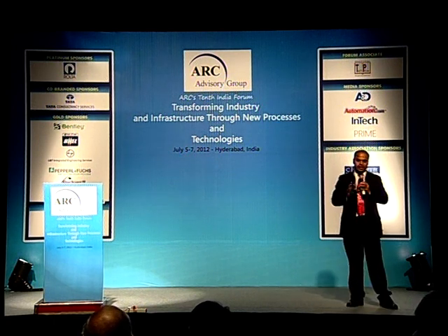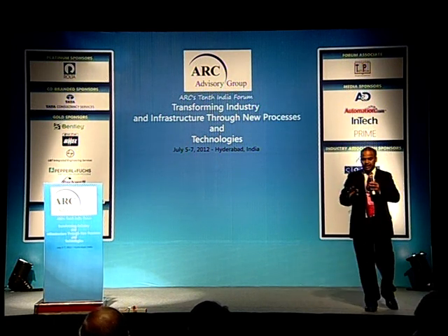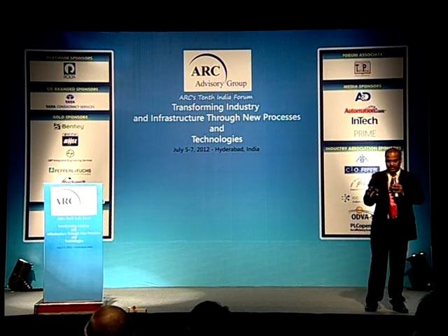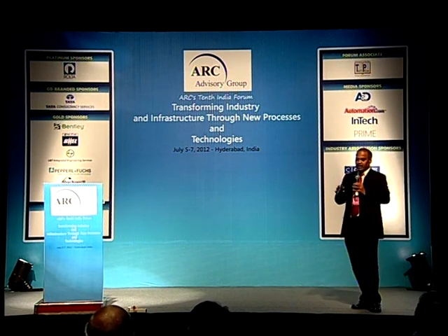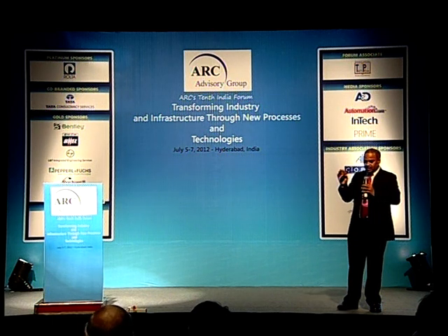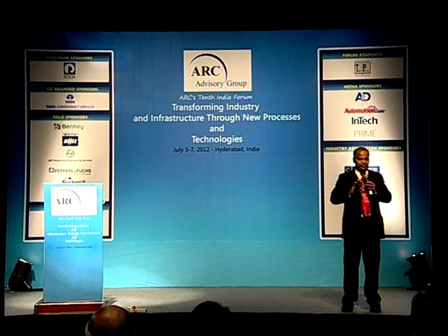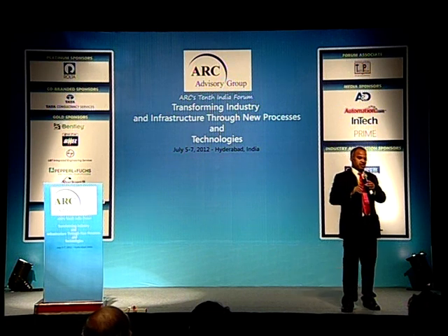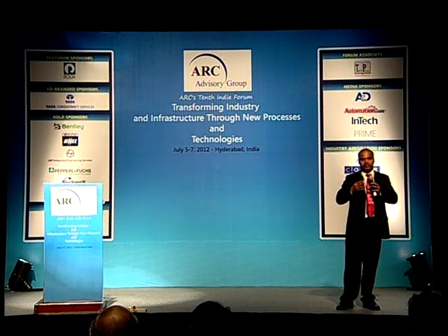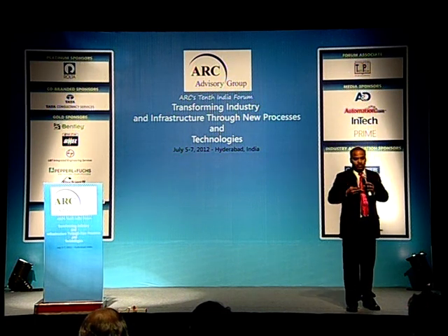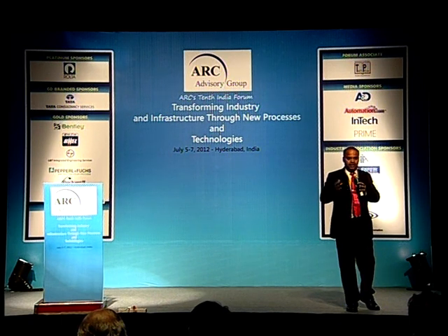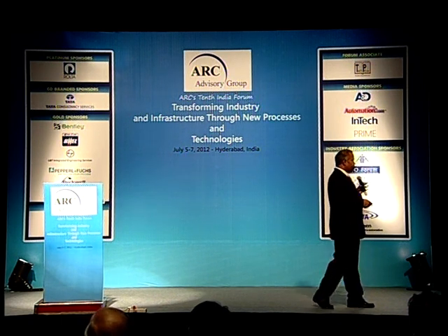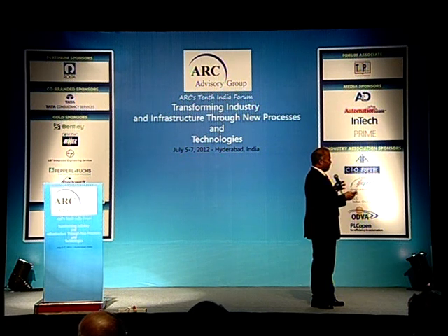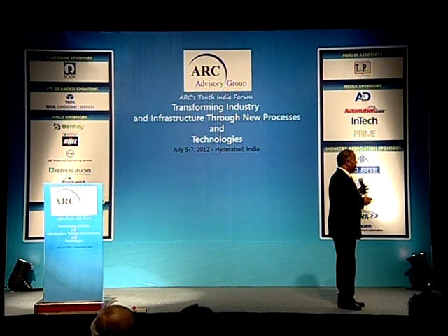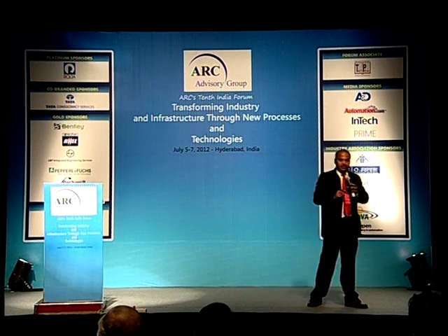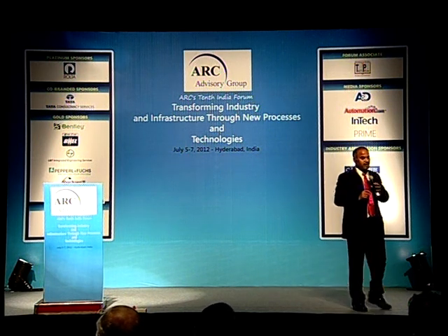This is one of the easiest methods, adoptable in almost every hazardous area location, not only in oil and gas but in different types of industries as well. It is good enough, almost perfect, when we have a conventional type of application. We have one device powered from a control room, which brings the voltage and current in a limited fashion, and that's enough. But when we move into different types of industries and go to the Fieldbus level, there are different requirements, totally different from conventional requirements.